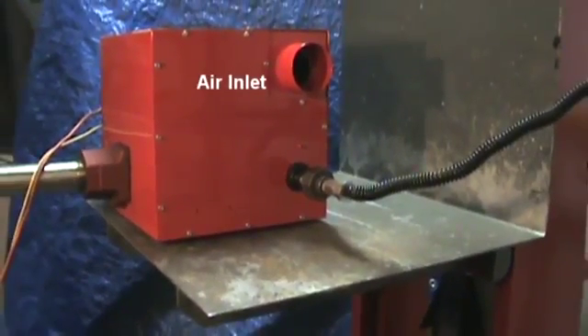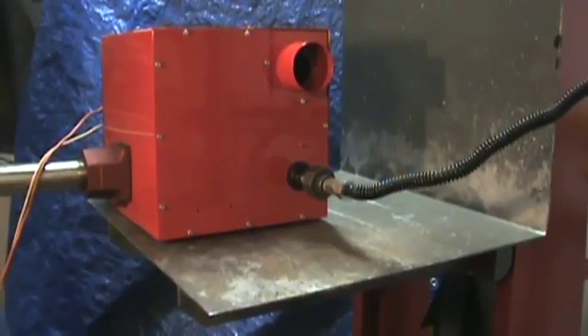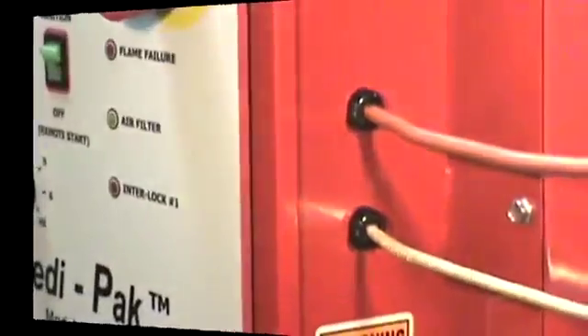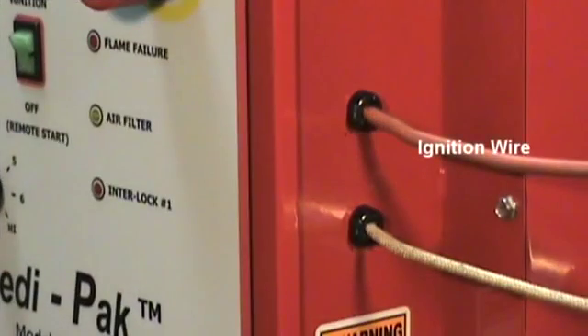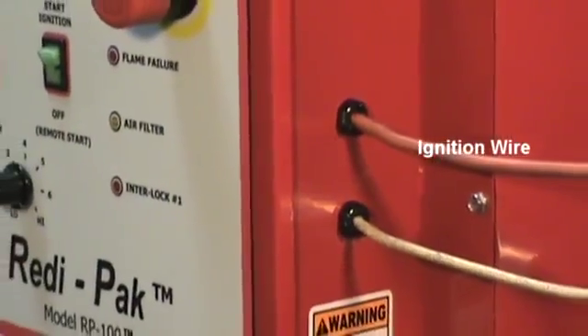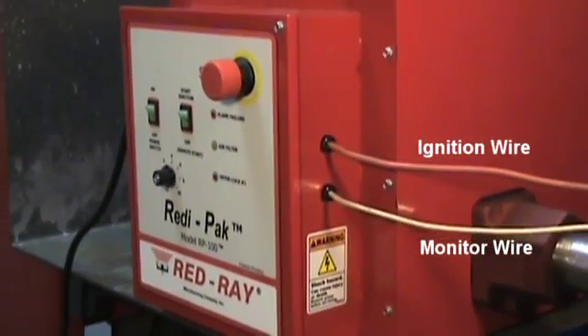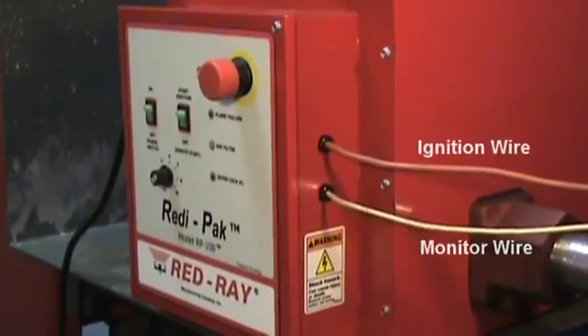The air intake tube leads to the filter compartment. Upon ignition, the gas valves will open and the pre-mixed blower will supply the combustion mixture to the burner. The ignition wire exits the control box and leads to the spark igniter. A flame electrode at the burner constantly monitors the presence of flame signal, which is sent back to the Redi-Pak by way of the monitor wire.